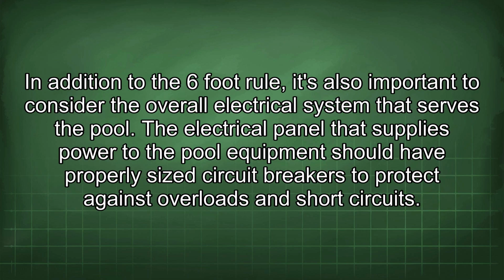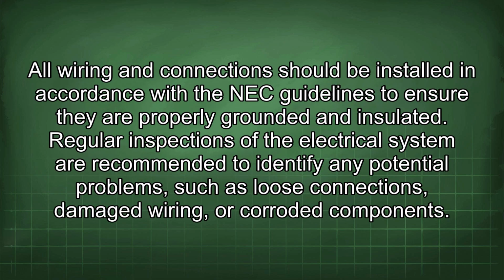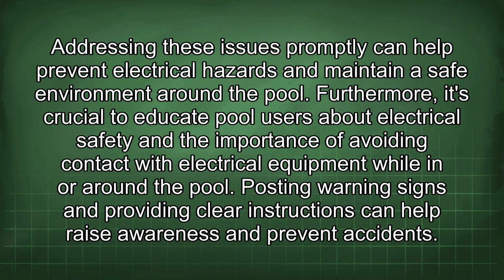In addition to the 6-foot rule, it's also important to consider the overall electrical system that serves the pool. The electrical panel that supplies power to the pool equipment should have properly sized circuit breakers to protect against overloads and short circuits. All wiring and connections should be installed in accordance with the NEC guidelines to ensure they are properly grounded and insulated. Regular inspections of the electrical system are recommended to identify any potential problems, such as loose connections, damaged wiring, or corroded components. Addressing these issues promptly can help prevent electrical hazards and maintain a safe environment around the pool.